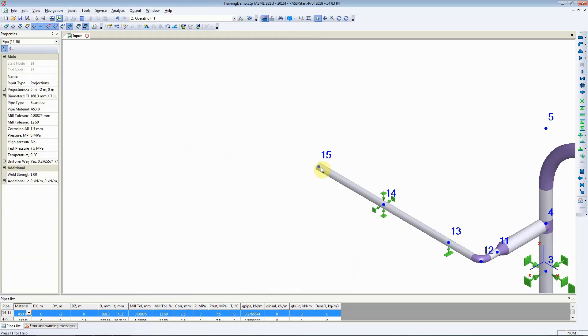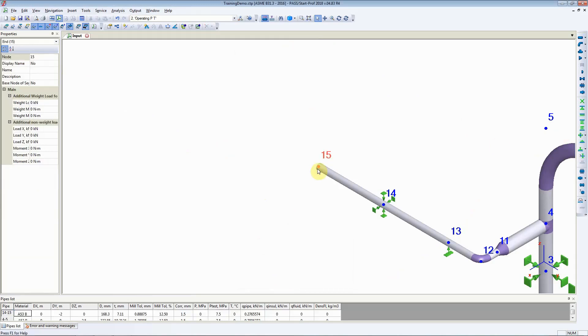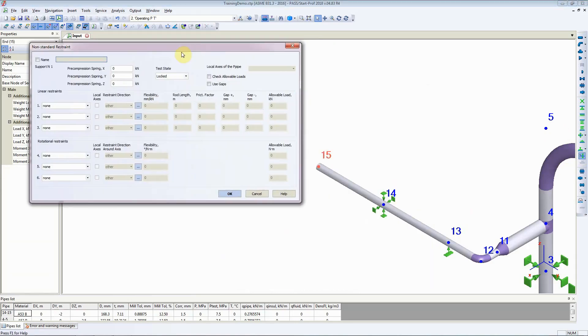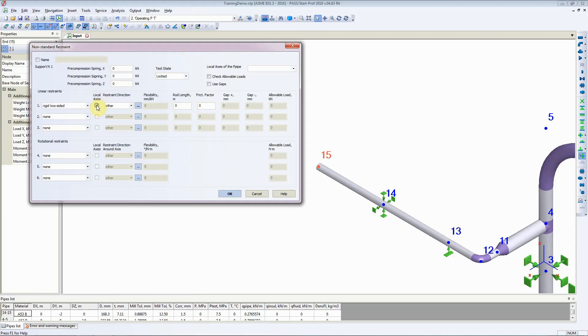At this node, we would like to add a limit stop. To add a line stop to node number 15, click on Insert Non-Standard Restraint. StartProf opens up a large window with lots of options. In this scenario, we just want a rigid two-sided restraint on the local axis in the axial direction. So we'll click on XM Axial, and then click on OK — StartProf will add a line stop.